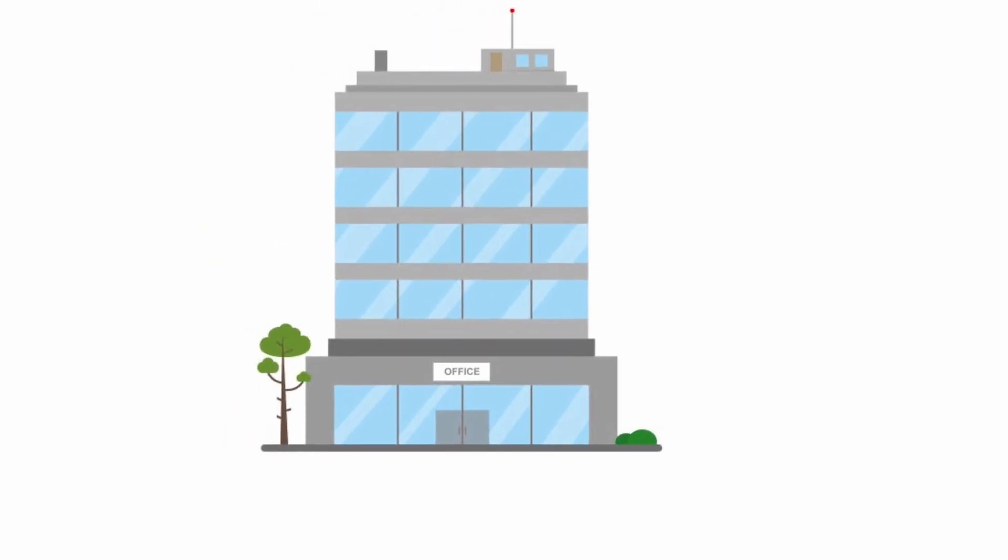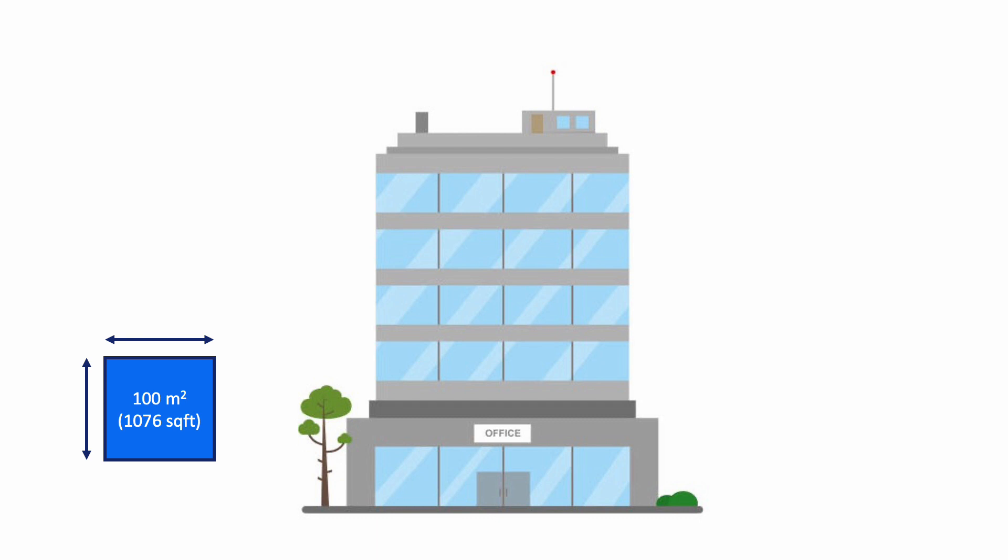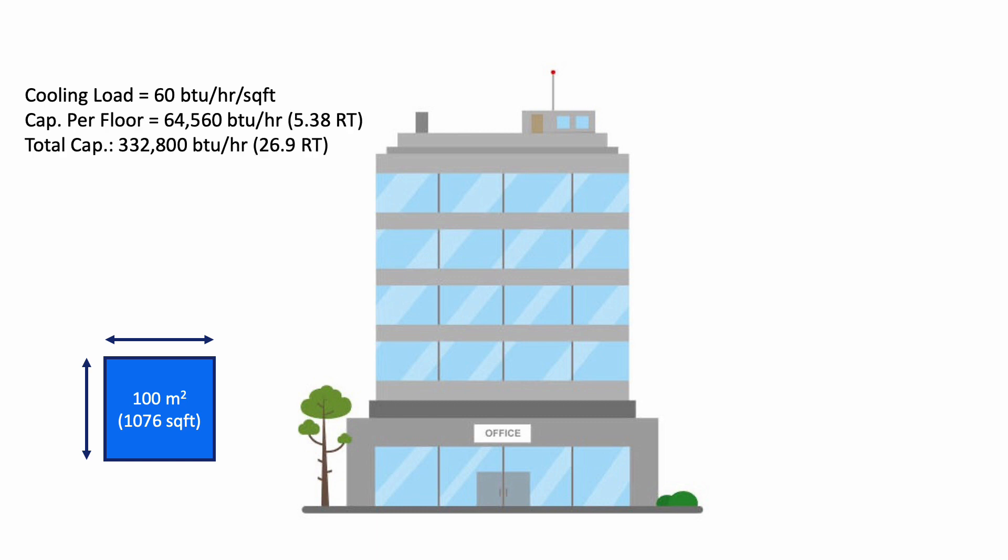Let's see a very typical example where VRF system is really one of the best choice in the building. An office building. Office building is like not big, not small, a medium size, five floors. Then the floor area, maybe about 1000 square feet per floor. Then let's say we use a rule of thumb to calculate, 60 BTU, then you have per floor 5.5 ton, then the total capacity is 27 ton. So 27 ton is within the range of a VRF system.